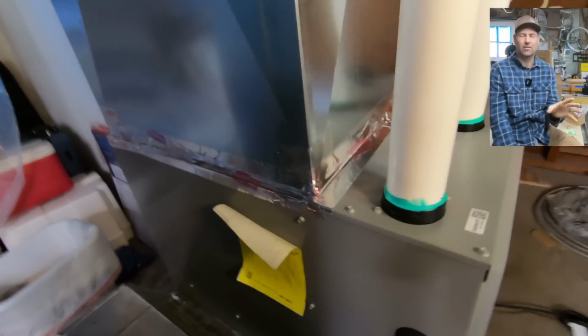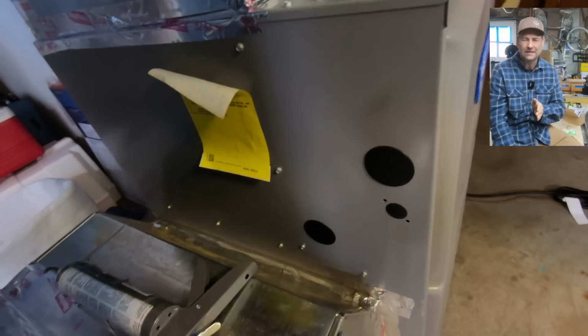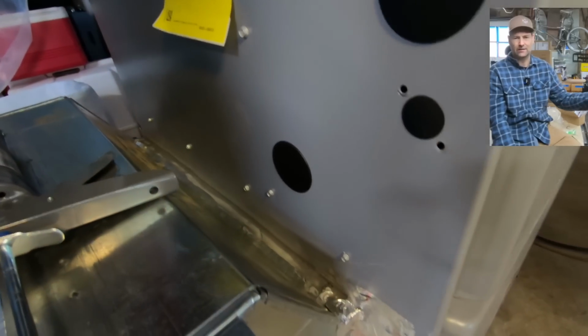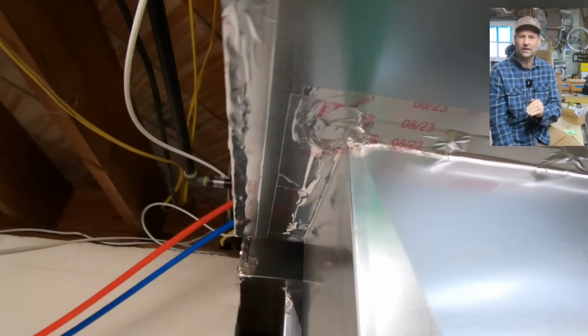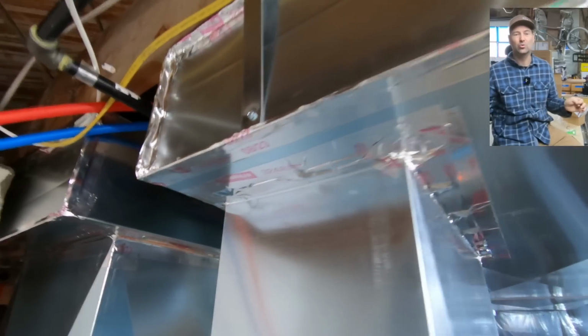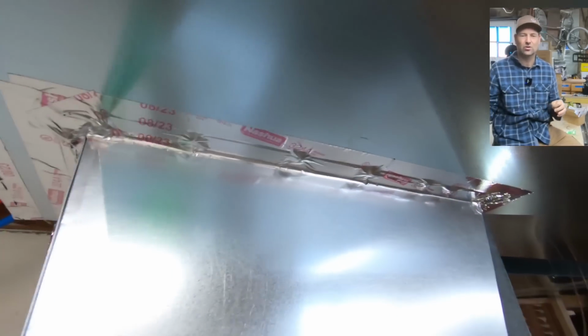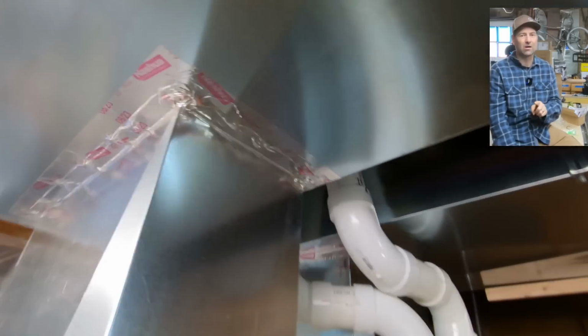Something else to expect: if you have a forced heating system, your fan that pushes the air is probably going to be set on its medium setting. That squirrel cage fan shown in this video has multiple speed settings available. You will have your cooling set on the highest fan speed, while your heating will most likely be set on the medium fan speed. That's what you want. So if you're uncomfortable with the noise during heating, and you later opt to add an A coil and condenser, you're going to have more air pushing through there.